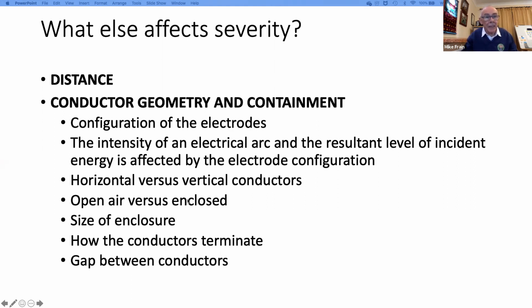Horizontal versus vertical conductors will make a difference. Talk about that later. Open air versus enclosed will make a difference. The size of the enclosure will make a difference. And how the conductors terminate will make a difference. And also the gap between conductors. I don't think it takes much imagination to know that if you increase the gap, it'll actually reduce the amount of arcing current. But all those items are taken into the calculations for IEEE 1584, which I mentioned earlier and I'll refer to again later.